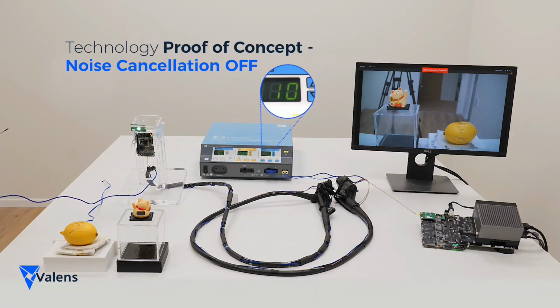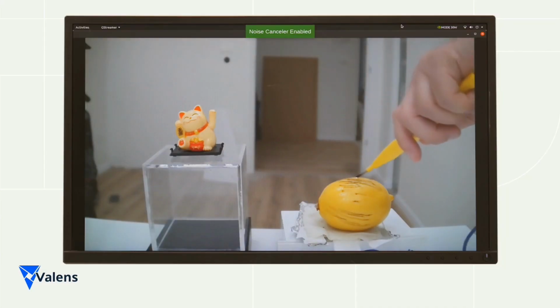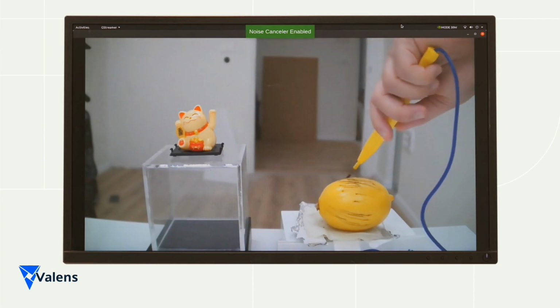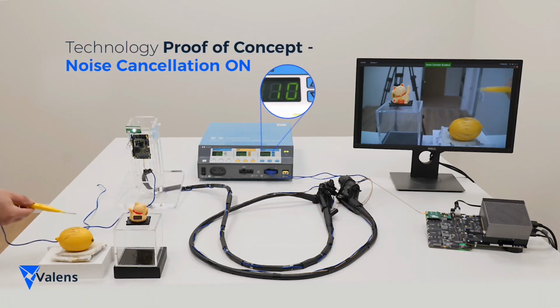Turning on the noise generator to a level of just 10 watts and using the probe on a lemon simulating a patient, the link fails and the video freezes. Now let's repeat the process, but this time turning on the Valens VA7000's built-in electrosurgical noise canceller. As you can see, the video remains picture perfect at the same level of 10 watts. We can do it again, turning the noise higher, and again, the video remains uninterrupted.